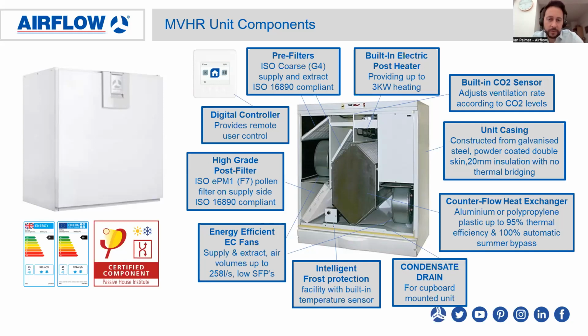You've got high-grade filters in these units. So again, the ISO EPM1 F7 pollen filters on the supply side. This meets ISO 16890. You've got digital controllers that can be supplied with the unit. They also have an internet connection, so the units can be connected up to the internet, and they can be remotely accessed from anywhere. Of course, they'll be password protected. The pre-filter would be an ISO coarse, G4.